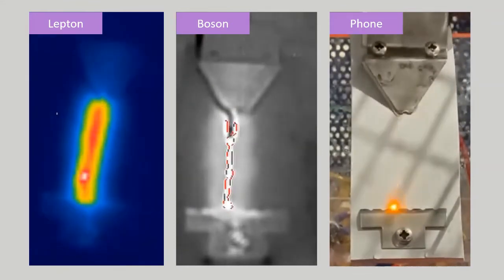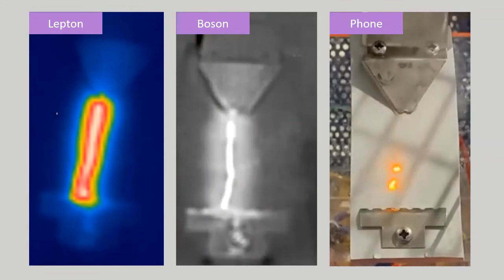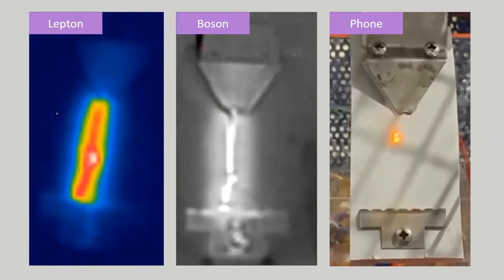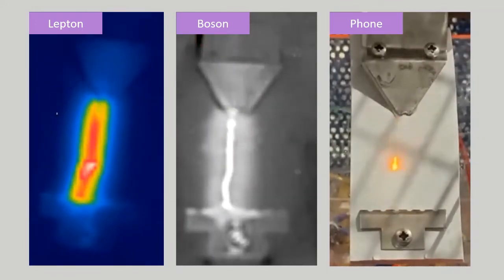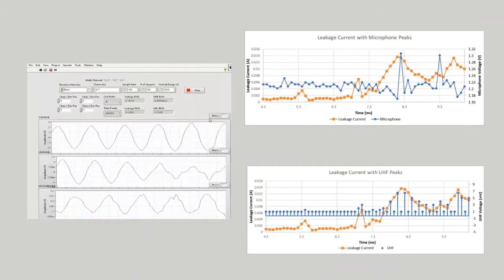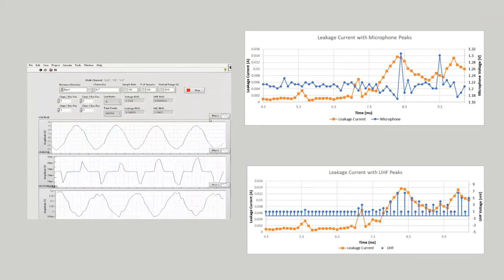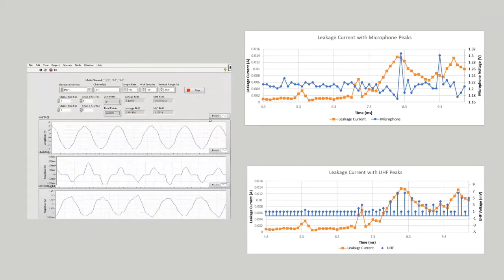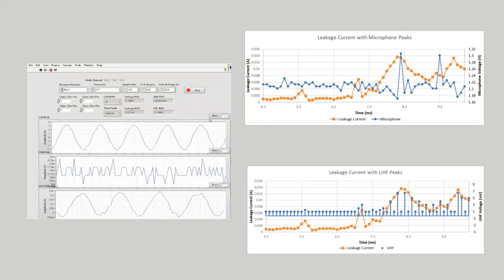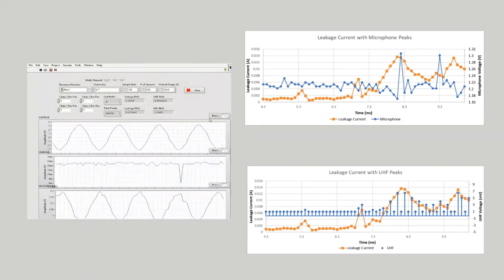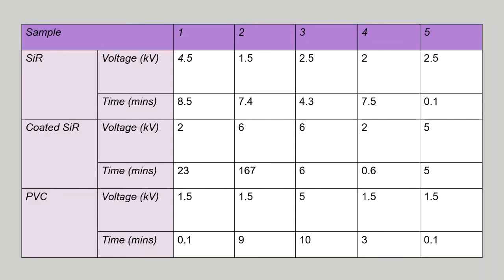It also allowed for observations of how the heat spreads throughout the sample, encouraging discharges to take place, seen as orange bands of light. The UHF and microphone outputs showed linked activity between discharges and leakage current spikes. A benefit of these sensors is that they are non-contact and therefore may be used for in-field testing. Results from the time-till breakdown showed coated silicone lasted for longer periods of time at higher voltages compared to non-coated silicone, which suggests coatings can prolong the lifetime of an insulator.